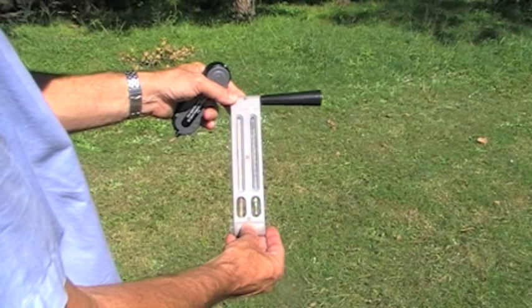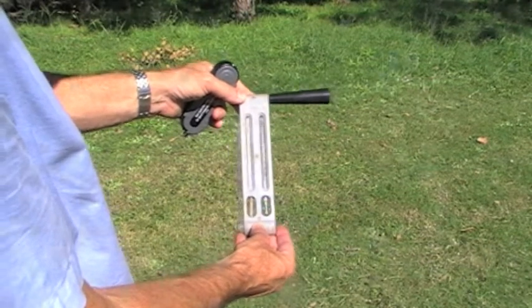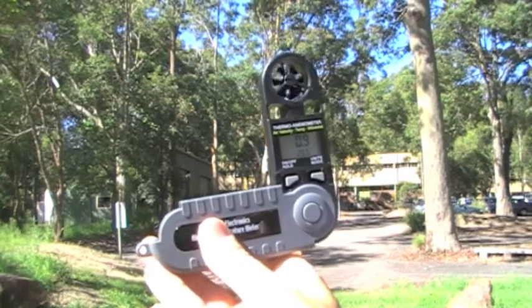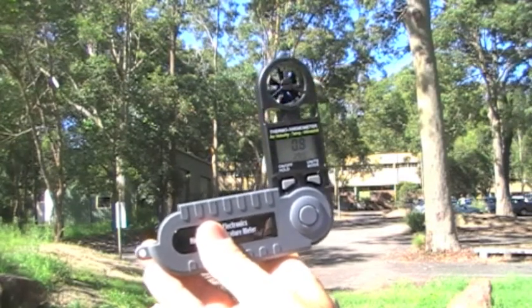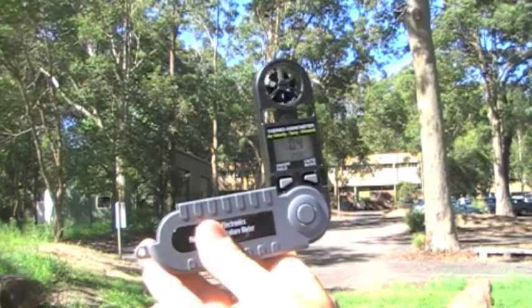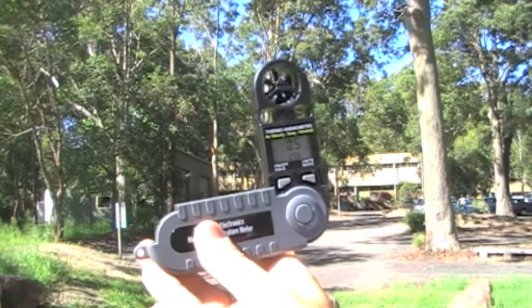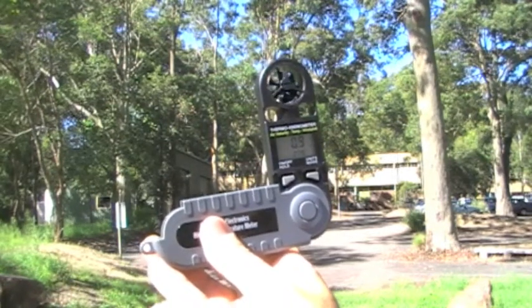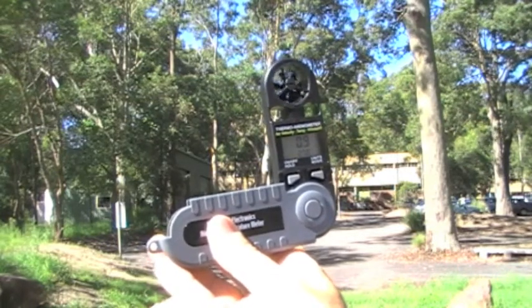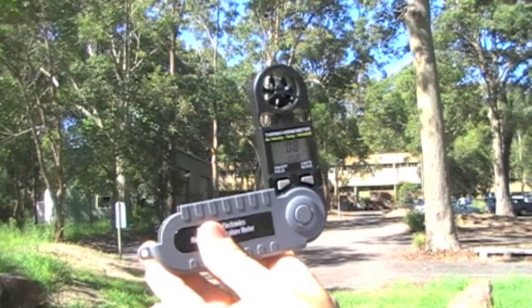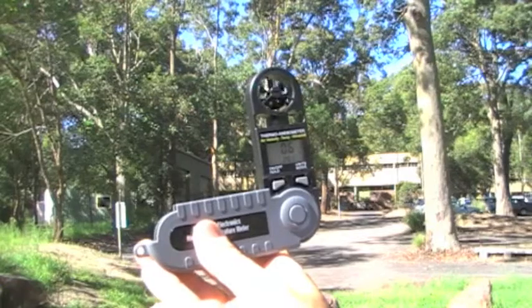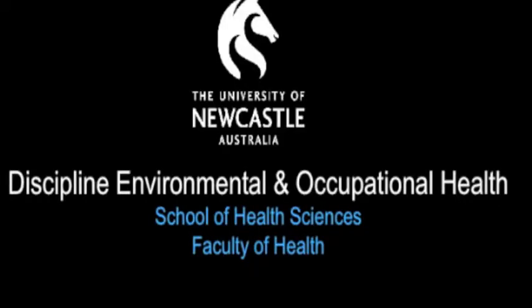This is a small anemometer which is using air movement to move vanes much like a windmill and recording the air movement in meters per second. We also have the air temperature displayed below it so currently the air movement is 0.9 meters per second and the air temperature is around 27.5 degrees centigrade.